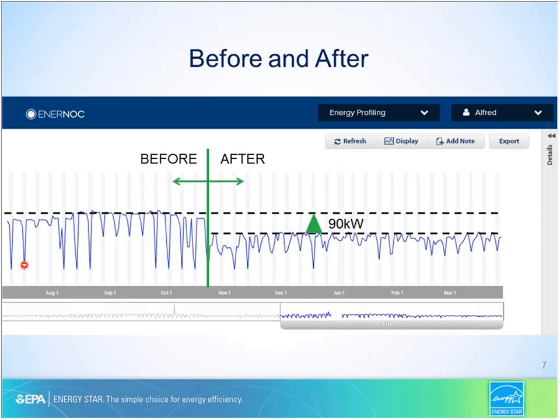Here's a graph of the electricity usage by these elevators before and after the regenerative drives were put in. Each hump represents one day of real-time electric use. Before the drives were installed, we had about three weeks of data; after they were installed and operational, we've got about four weeks of data. As you can see, there's a solid reduction of about 90 kilowatts of demand every day.